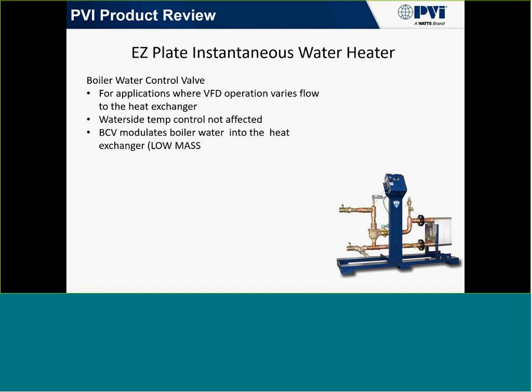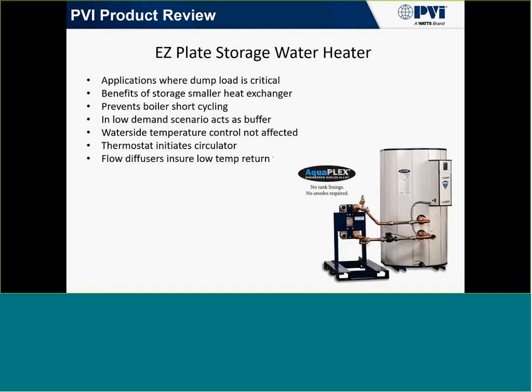If we incorporate that type into a storage tank, we can approach that as the same type of sizing scenario as the COBREX storage. Another benefit of this type of design is the pressure loss in your system. If we incorporate this with a storage water tank, you're not going to see that pressure drop inside your system that you would traditionally see going through an instantaneous plate and frame heat exchanger.